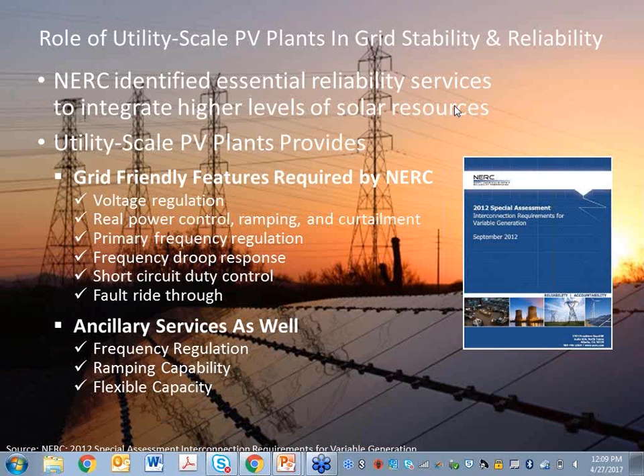Okay, thank you. Another question: do the inverters have any special feature to enable these controls? As I explained, most utility scale inverters are capable of providing PQ controls. They generally operate at a much faster rate—switching frequencies on the order of several kilohertz—and as long as the inverter manufacturer ensures those capabilities are available externally from a controller, then yes, it is available.